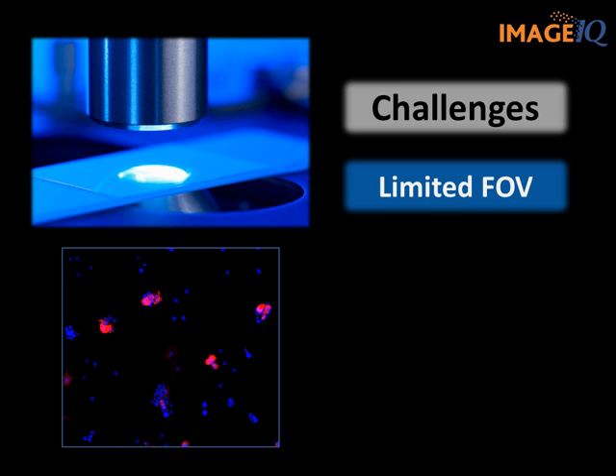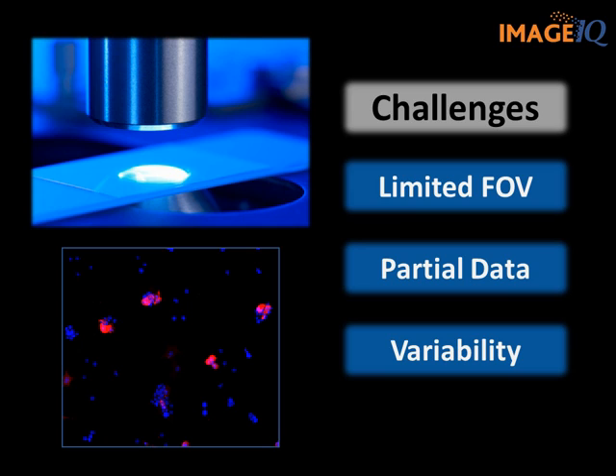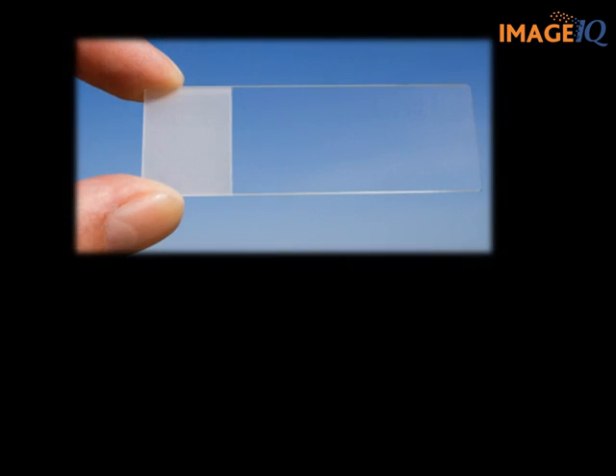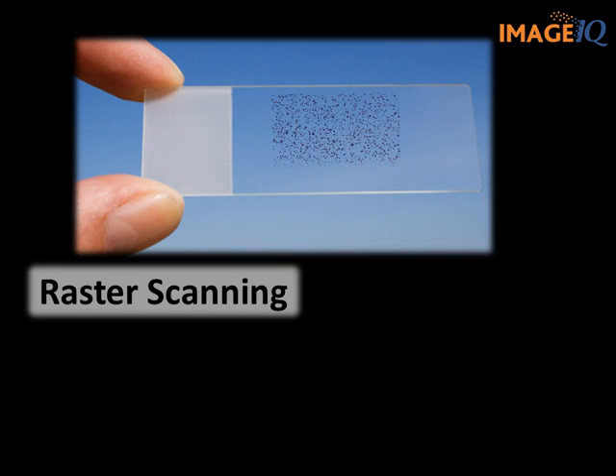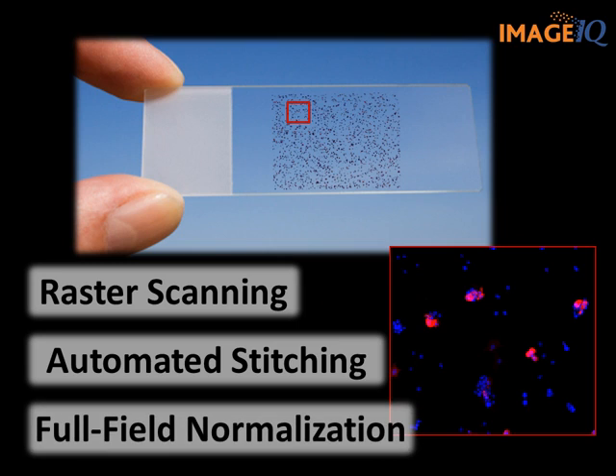The first challenge was finding a way to image and analyze the entire cell culture surface rather than simply looking at a limited field of view, which is generally afforded when looking through a microscope during manual scoring. We utilized a technique called large field of view image acquisition. This type of imaging requires a wide field microscope fitted with a motorized stage. With this hardware setup, we can raster scan across an entire cell culture surface area on a slide or well and stitch together high magnification image tiles. The result is a very high resolution image that provides the detail necessary for accurate image segmentation and analysis.